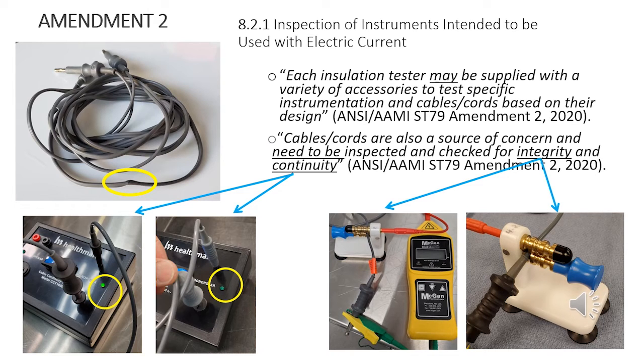So let's break down what AAMI is actually stating in regards to integrity. Integrity would be the outside of the cable and cord, like you see in the pictures on the bottom right, where the cord is put through this specific wire tester, looking at the different diameters. As you can see, there are three listed, and then you find the right fit, turn on the insulation tester to a specific voltage, and run the cable through it. If there were any nicks in that cable, it would actually alarm.